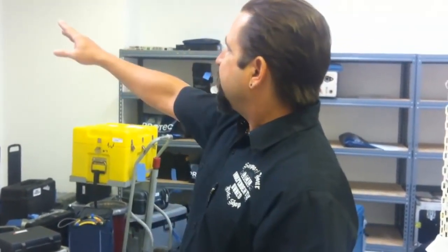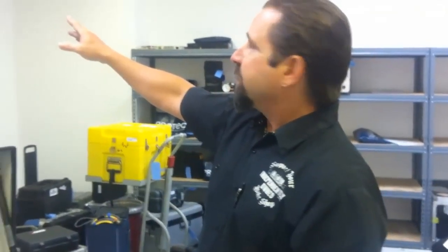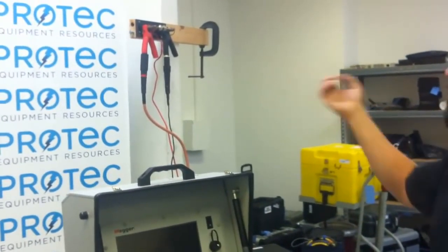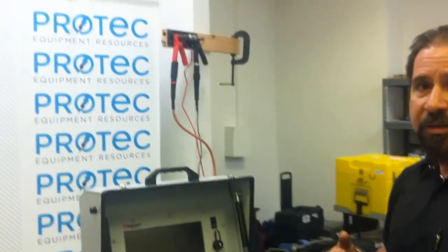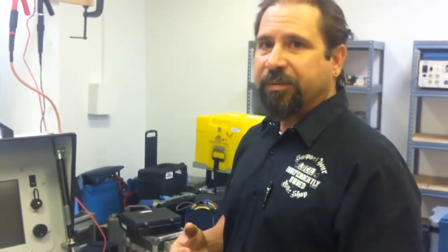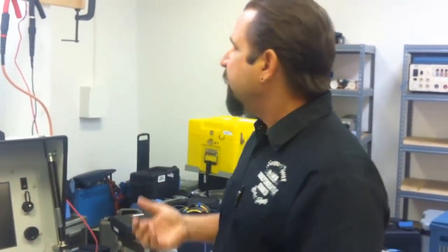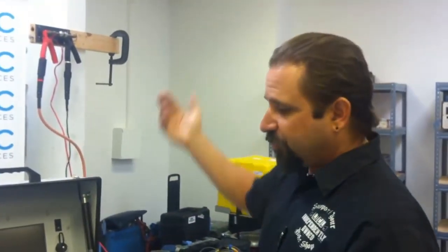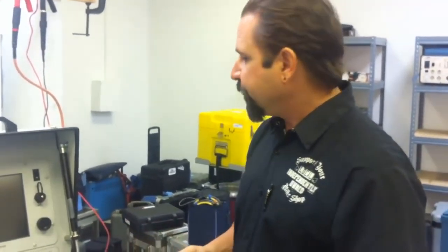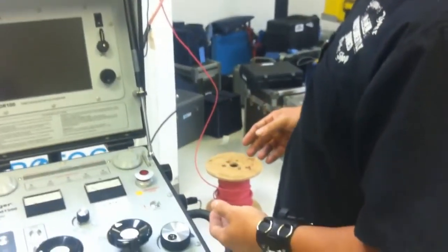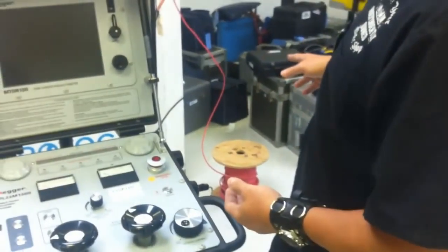Okay, we've got the cables and everything of our PFL22 system all hooked up. Our test fixture basically is just a wall-mounted spark gap so that we're able to go ahead and deliver surges to it, validate that the instrument is discharging properly, we're getting proper discharge and energy transfer. We can also do the proof burn down technique, make sure that all the circuitry is working and functional on that. I have approximately 200 feet of cable connected up to this as well.